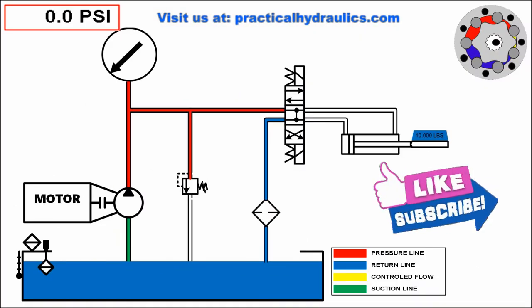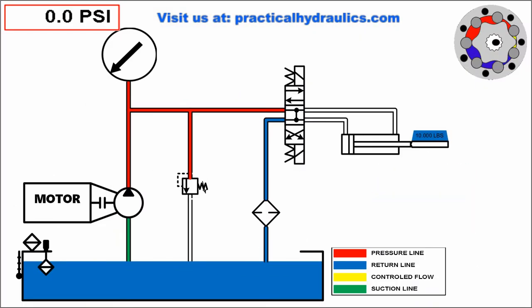The topic we offer today is courtesy of Practical Hydraulics. Load-induced pressure is defined as pressure generated from the load or force on the actuator. The effective area of the cylinder piston is the area available for force generation.